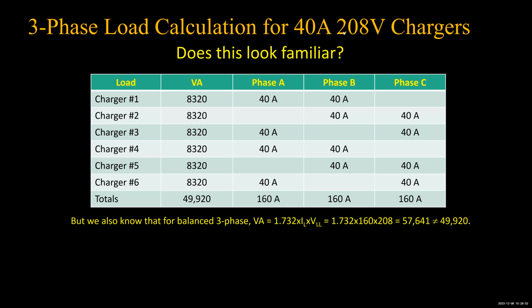All right, but presumably that means that the neutral current is comparable to the line currents. And presumably, if that's really the case, then maybe you don't have to derate the conductors. Maybe you just have to reset the chargers so that they charge at the next lower charging rate. So okay, I'm sure this is going to get a lot of attention, because if this is really true that it's happening in a local jurisdiction, then that's definitely going to get attention. And this is one of those things that the ever-changing world, by next year, people will have more data, and we may see changes in the 2026 National Electrical Code.